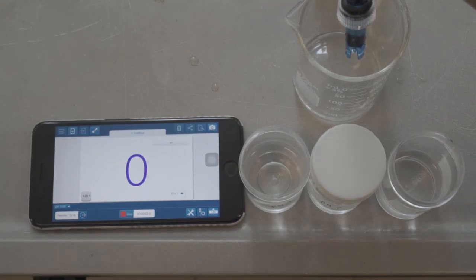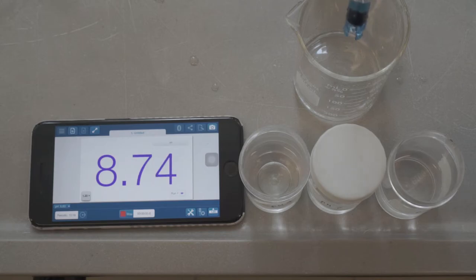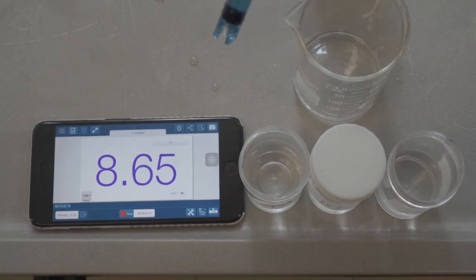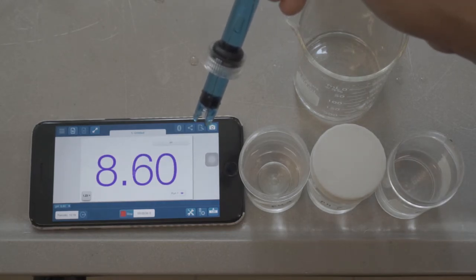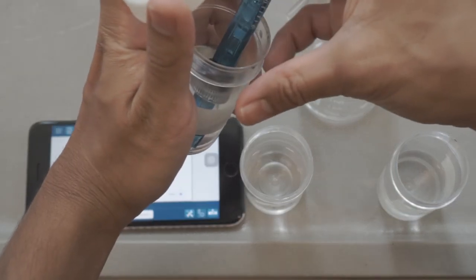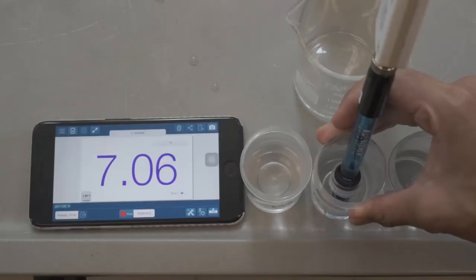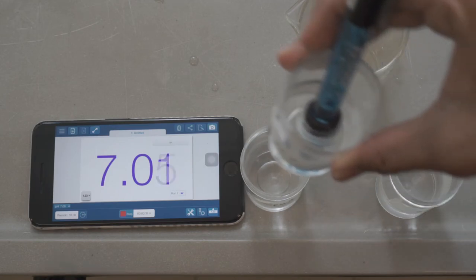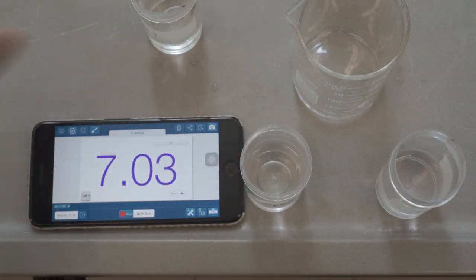Press Start. Place the end of the probe into the pH 7 solution. The registered pH should be close to pH 7. You have now completed the pH sensor calibration. You may now begin with your experiment.